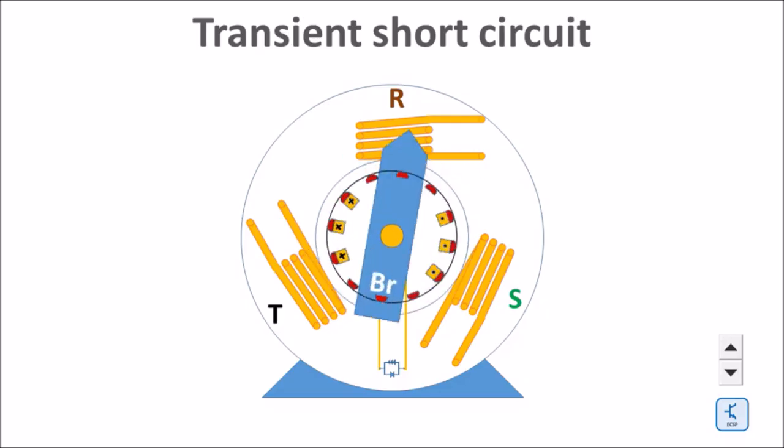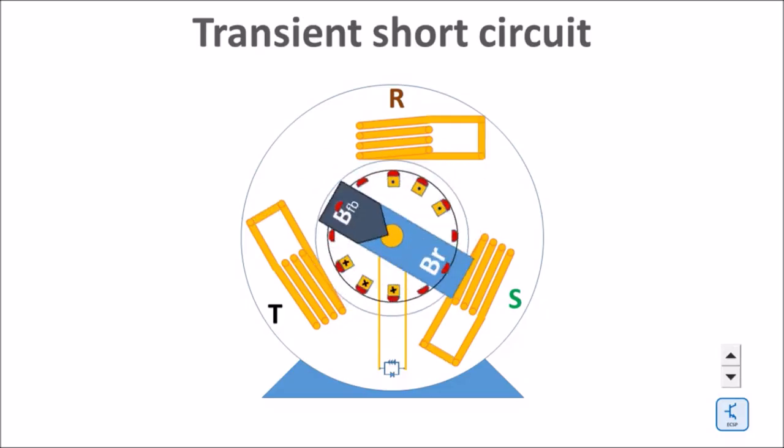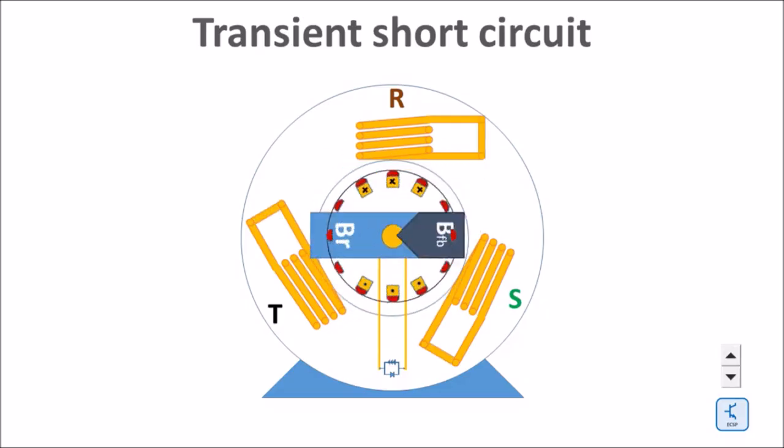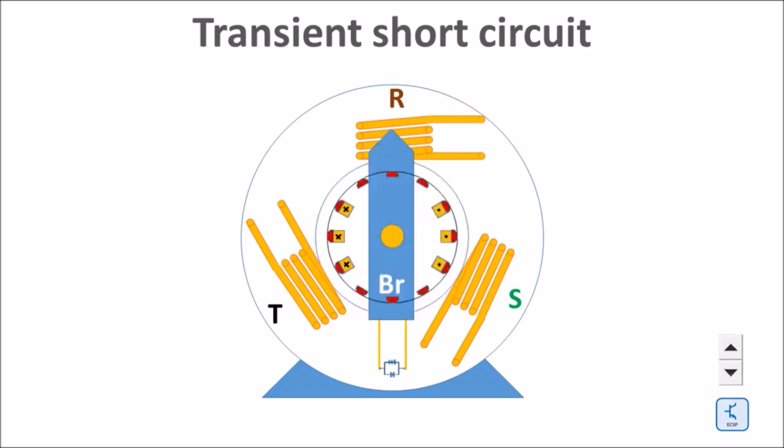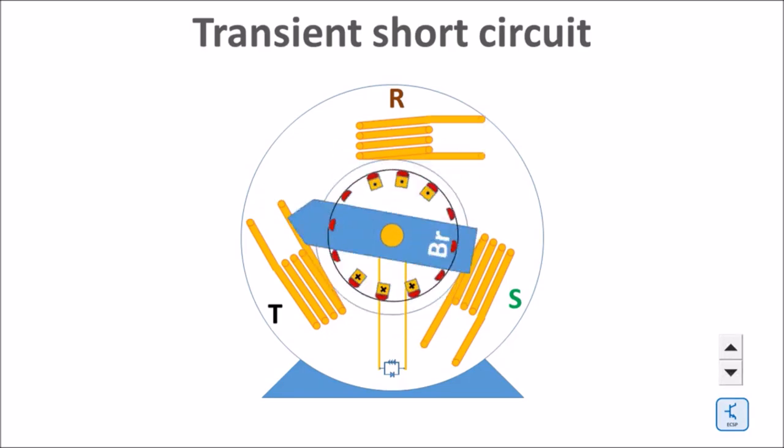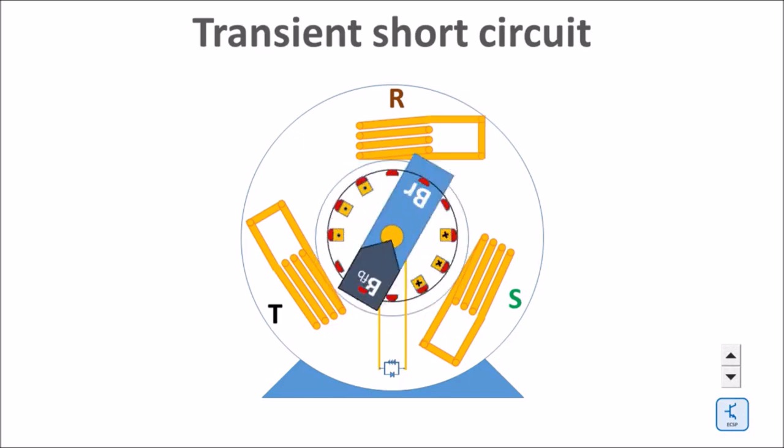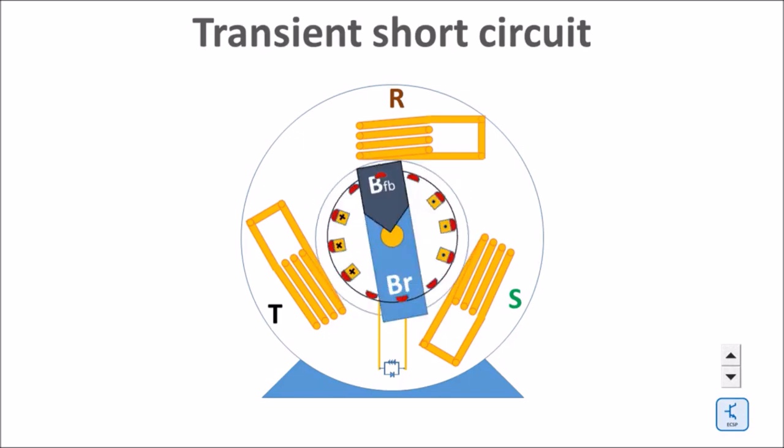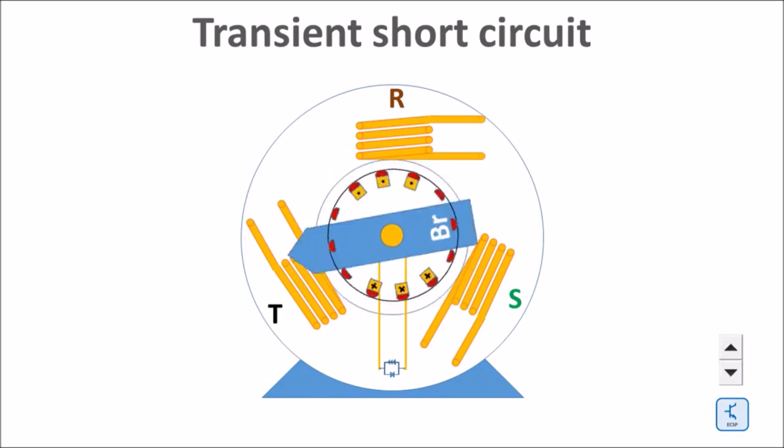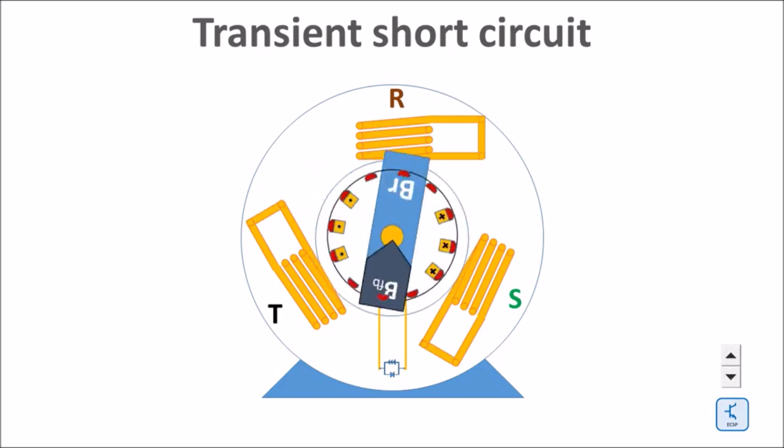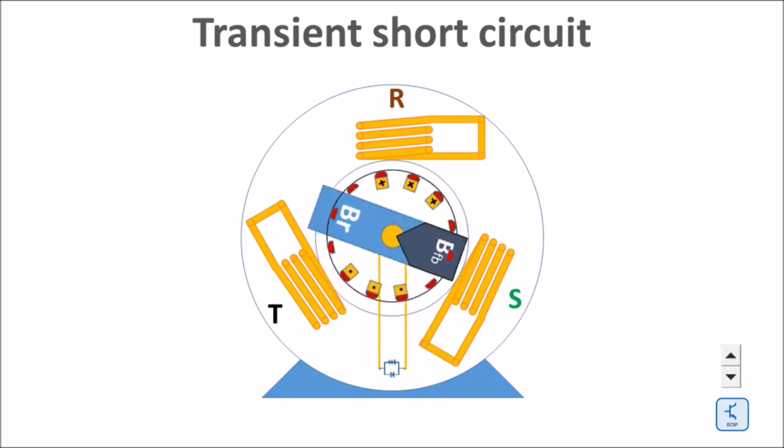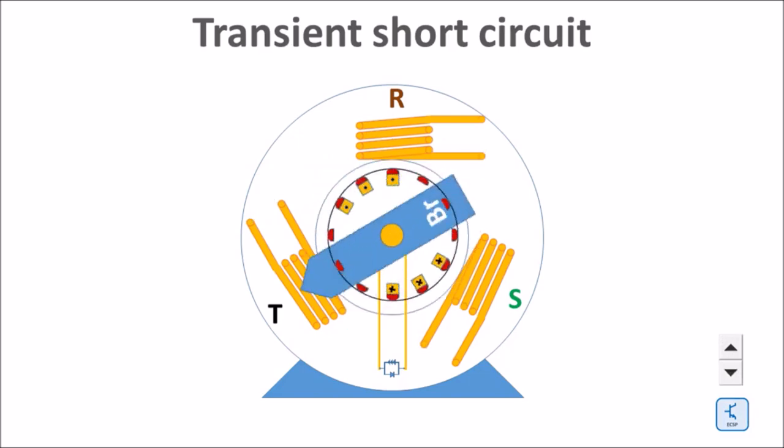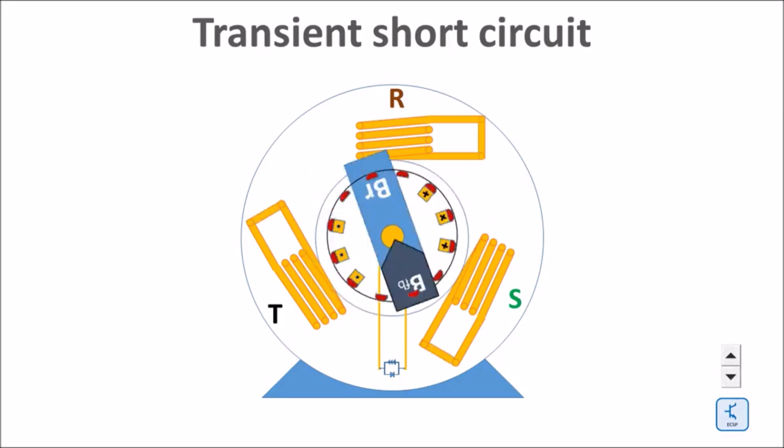At the instance of the short circuit, the three stator phases produce a rotating counter field—the field in gray—which tries to penetrate the rotor. In order to better understand what happens with the rotor field, let's now sit on the rotor and let the stator rotate around the rotor.